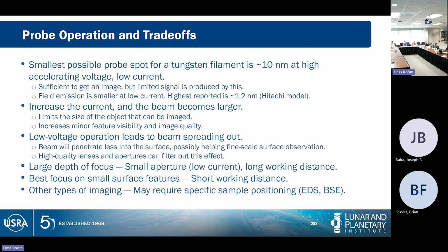The other thing we mentioned was the depth of field. Well, we have the ability to focus on a range of depths. If I want to manage depth of field, a low current, small aperture, and positioning my sample far away from the beam source will let me see something with a greater depth to it. So I can see around edges or see different features. On the other hand, if I bring my sample up, I get a better focus. The beam is much more tightly controlled, closer to the lenses.